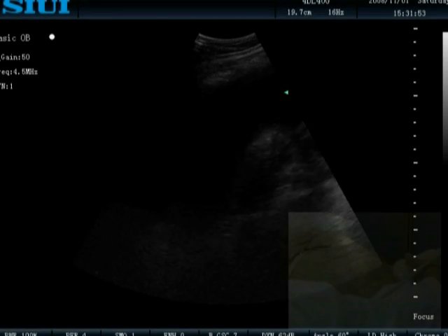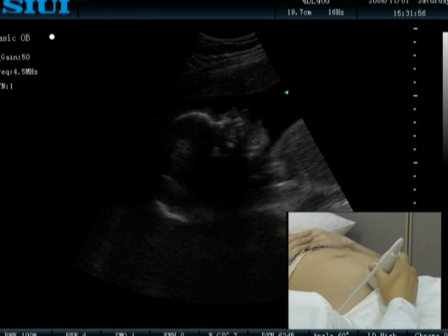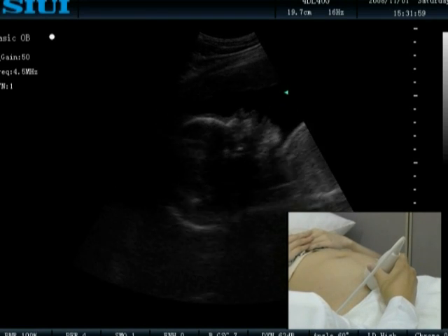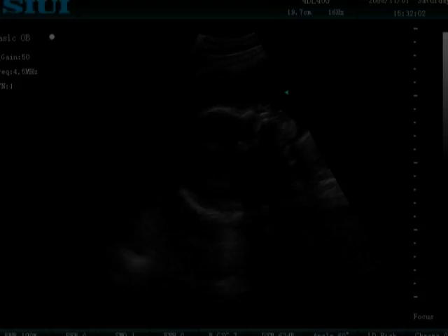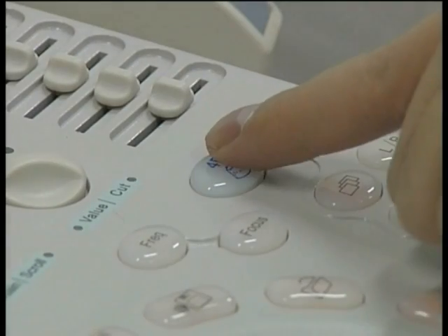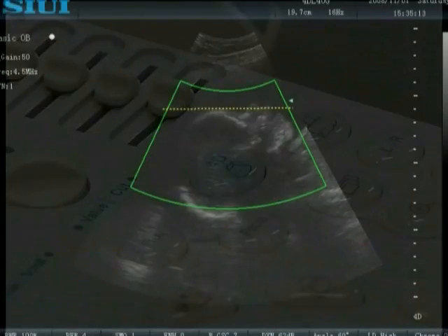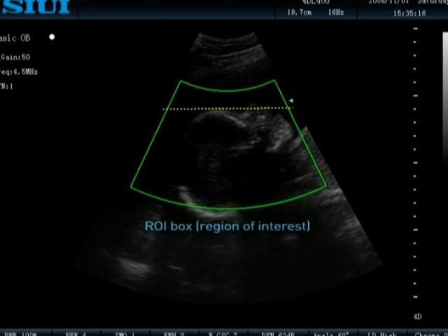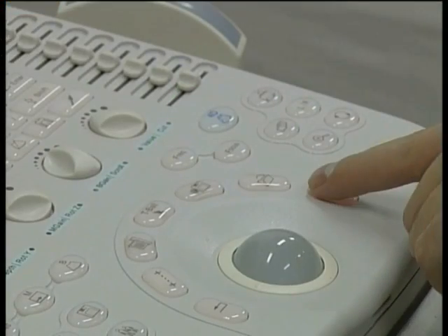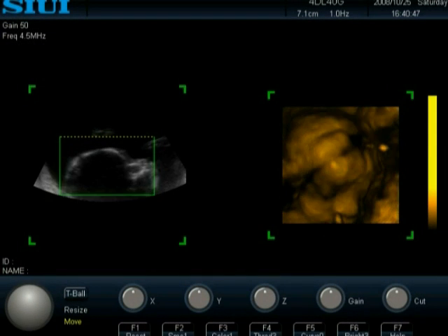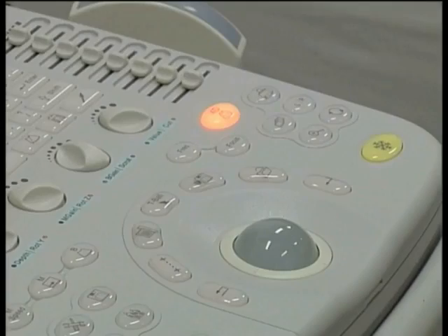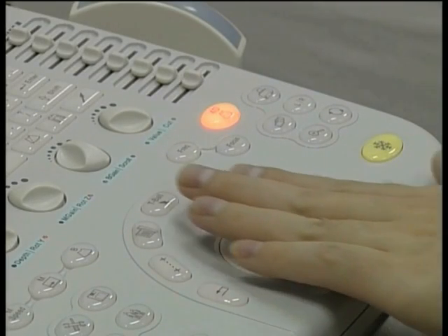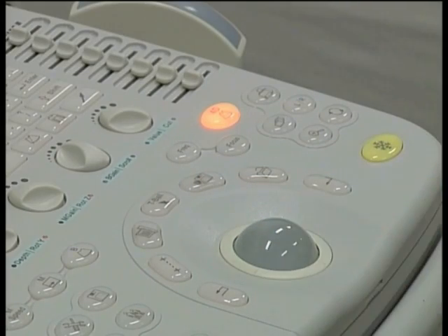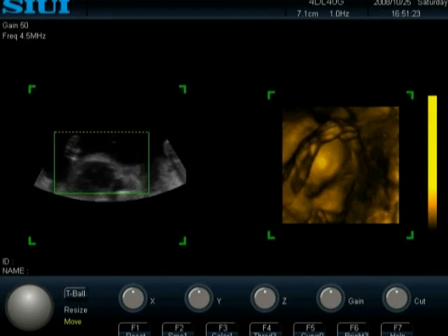Diagnostic process. Place the 4D transducer on the abdomen of the pregnant woman and find an appropriate section. Press the 4D key to invoke the ROI sampling box. Envelope the region to be acquired with the ROI box. Then press Enter to go to 4D mode. After entering 4D mode, use the trackball to shift the imaging select box on the left, and the resulting 4D image will be displayed on the right.